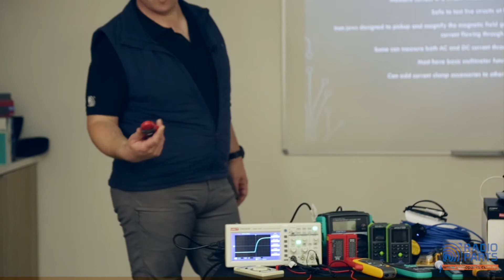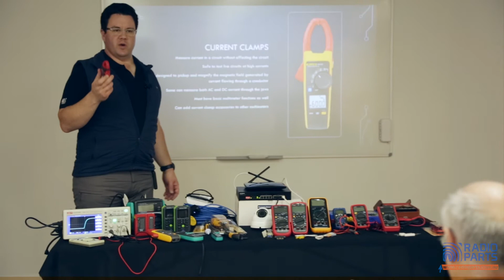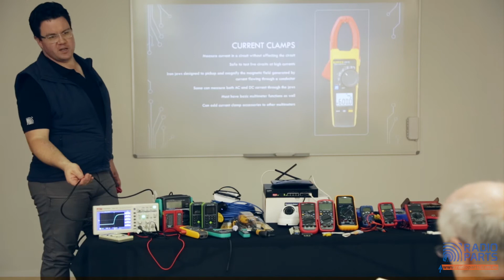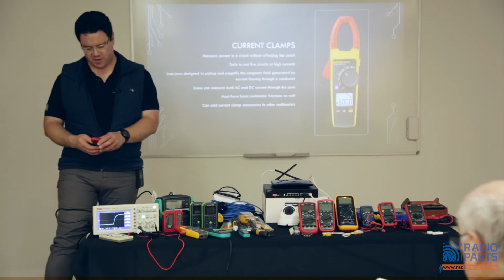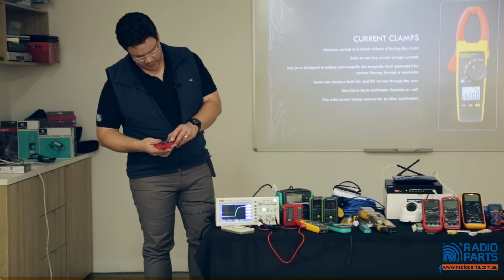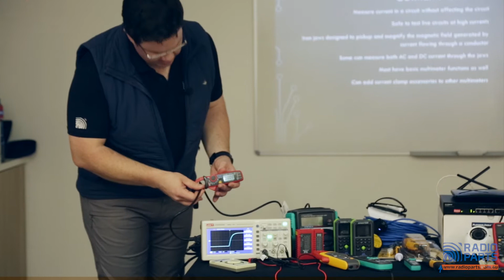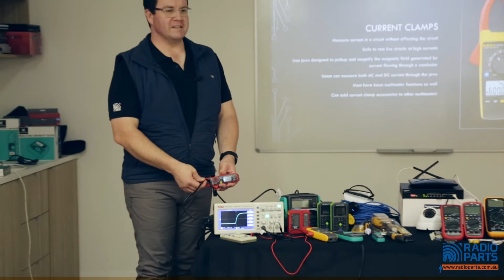I don't have to do anything to it. I can measure it while it's live, and I'm not going to hurt myself doing it. The problem is a current clamp works by measuring the magnetic field produced by a cable. When you've got an active, neutral and ground all running through the same cable, you're cancelling out the magnetic fields from the cable you're interested in with the others in there. So to do this live, I put it into 2 amp mode, light on, and according to this there's no current running through it. So great, I can cut this cable open and start playing with it, right?